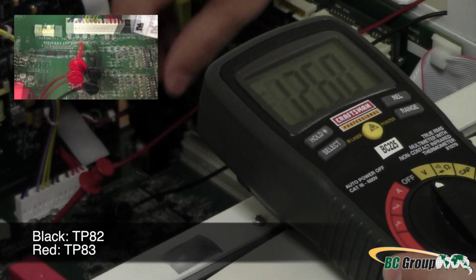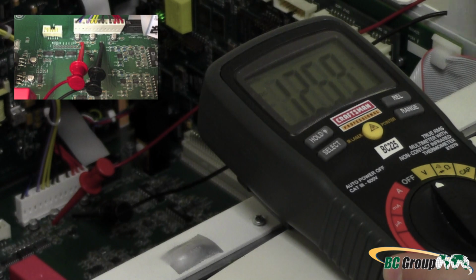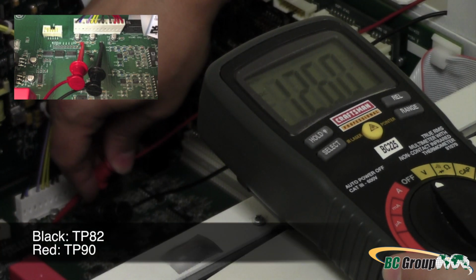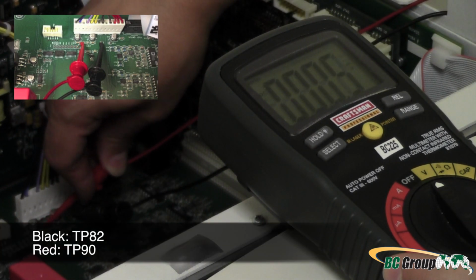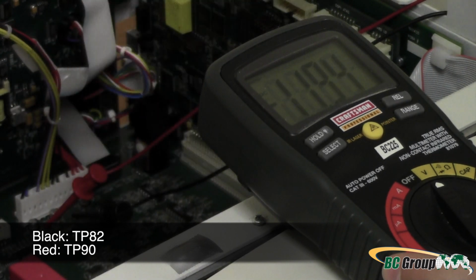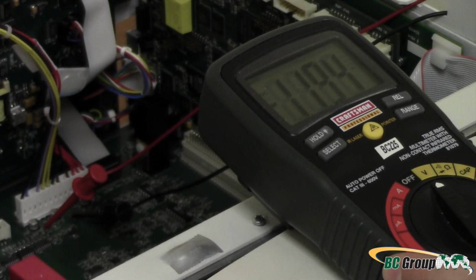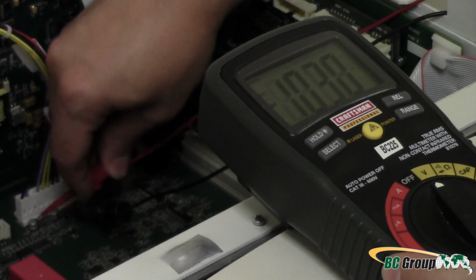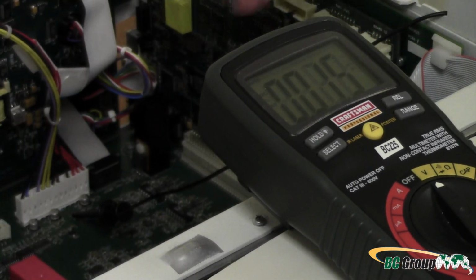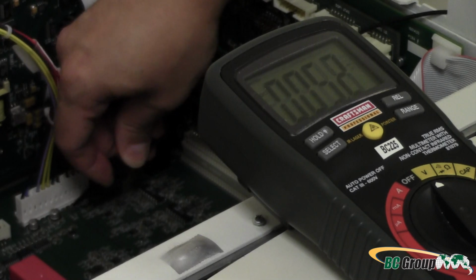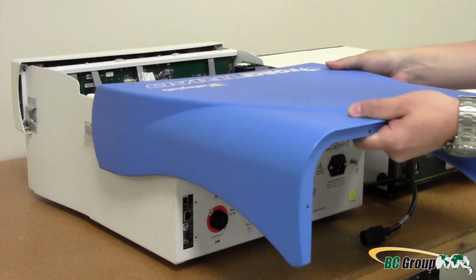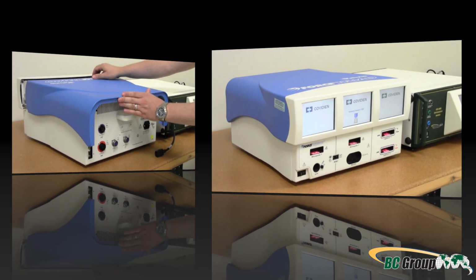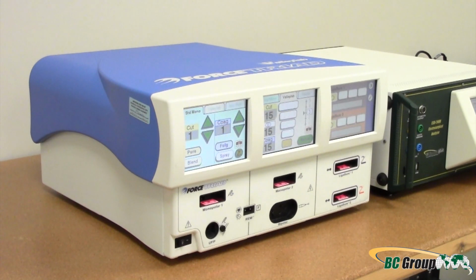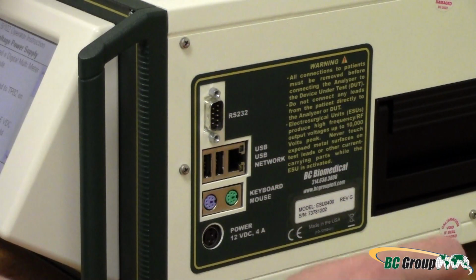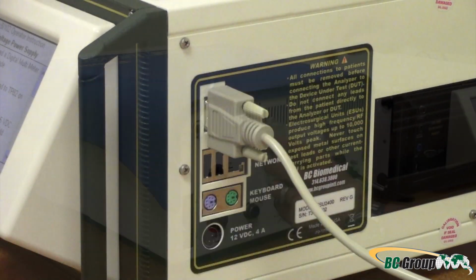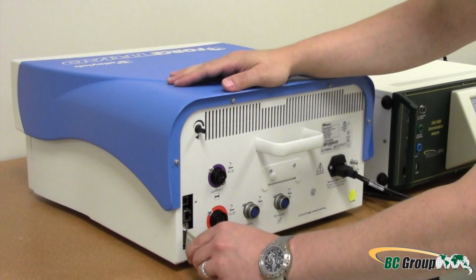This should read within 11.4 to 13.2 volts DC. Connect the positive lead to TP90 on the RF board. This should read within negative 12.36 to negative 11.64 volts DC. Disconnect the test leads from the generator and reinstall the cover. Cycle power on the generator, then connect a serial cable from the RS-232 port of the ESU-2400 to the RS-232 port on the back of the generator.